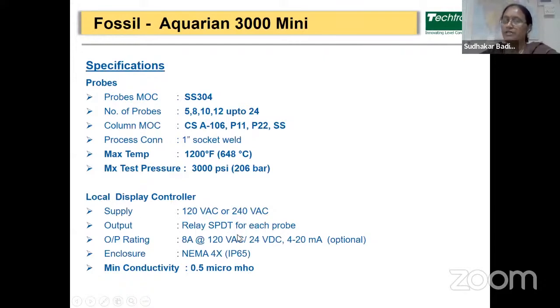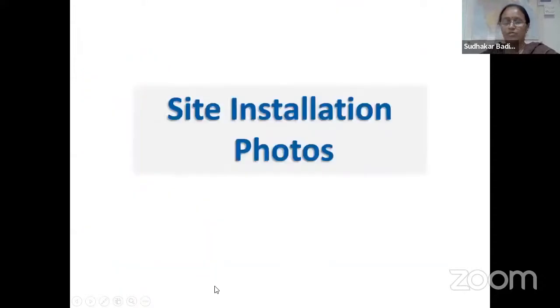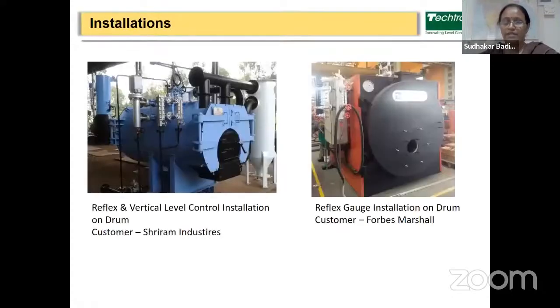Output will be relay SPDT for each probe. That is suitable for 8 ampere at 220 volt, 120 volt AC or 24 volt DC. Optionally, 4 to 20 milliampere is also available. And it is suitable for minimum conductivity of 0.5 micromho. Next, you can see the site installation photos of our instruments, which are mounted at various sites.